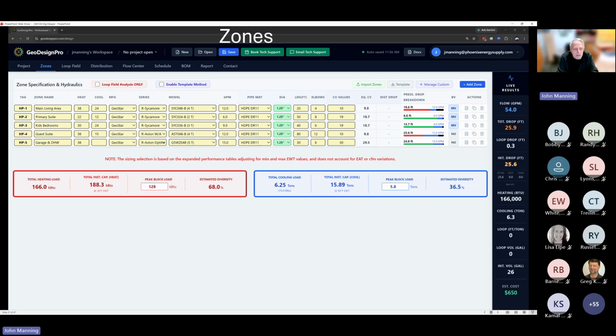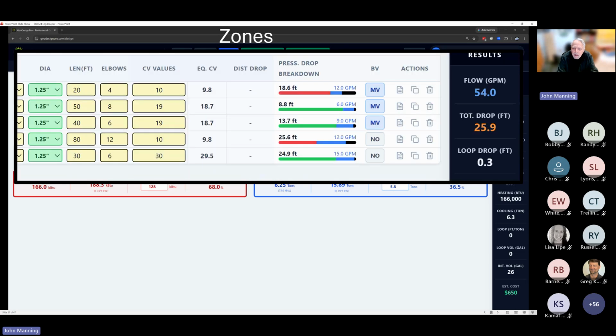The software will actually pick the right size heat pump based on your loads, but that too can be overridden if you feel it was off slightly. It will populate the flow rate at your GPM per ton that you specified. You can specify the pipe material, the diameter. In this particular case, I overrode the automatic suggested size, and I put 1.25 inches on every one. You define the length of that, how many elbows are in that circuit, any CV values of two-way valves or strainers, and so forth.